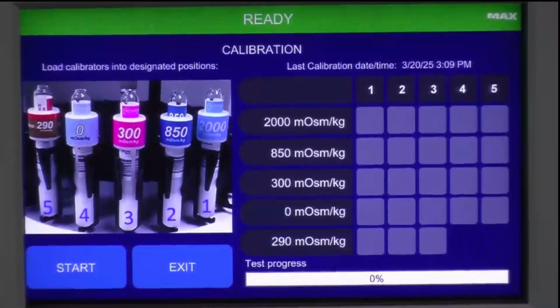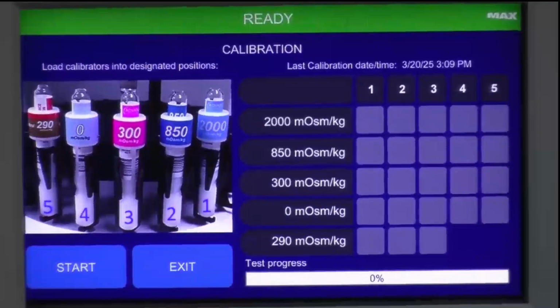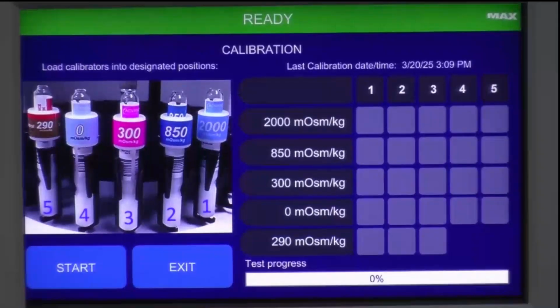Along the right, it's going to track the progress of the calibration. It's going to run 5 tests for each level. If the level passes, it's going to be a green check mark. If it fails, there's going to be a green X. A test for each standard can fail once. If it fails twice, you've got to start all over again. That doesn't typically happen. Calibration usually goes really smoothly, but that's what it's going to look like over here on the right.